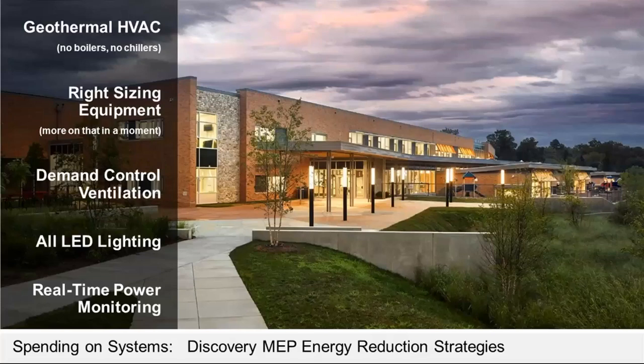Demand-controlled ventilation: there's a DOAS system with heat recovery and MERV 13 filters. Each individual geothermal heat pump for the classrooms has a MERV 11 filter, and all classrooms have at least two operable windows. So this building meets all of the CDC criteria for reopening during COVID.